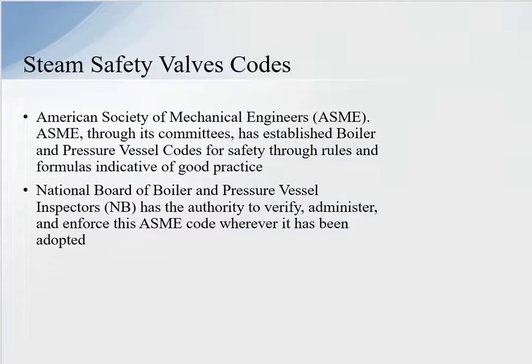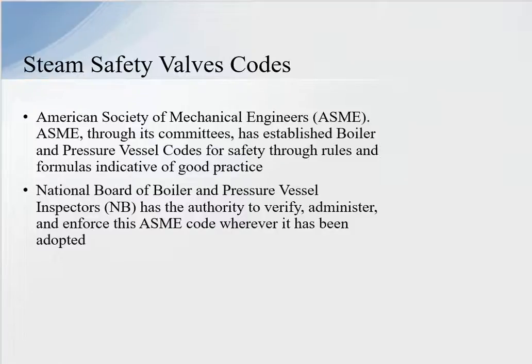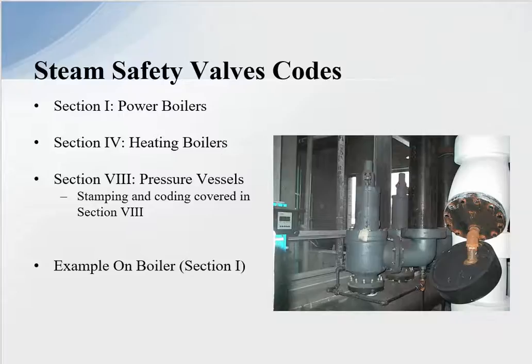The codes for steam safety valves are established by the American Society of Mechanical Engineers, ASME. Through its committees, ASME establishes boiler and pressure vessel codes for safety through rules and formulas indicating good practice. The National Board of Boiler and Pressure Vessel Inspectors has the authority to verify, administrate, and enforce the ASME code wherever it has been adopted. Therefore, any safety valve must follow the codes set out by ASME and under the jurisdiction of the National Board.